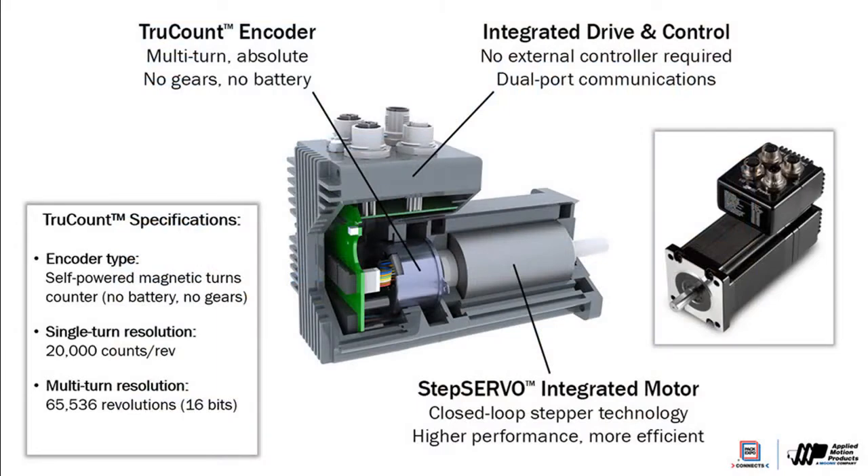The TrueCount Absolute Encoder is a high-resolution encoder able to resolve 20,000 unique positions within 360 degrees. It can also track 65,000 revolutions of the motor — what we call the turns counter. It uses a magnetic sensing element to keep track of the single-turn position, and it uses the turns counter to track the number of revolutions, clockwise or counterclockwise, from the home position.